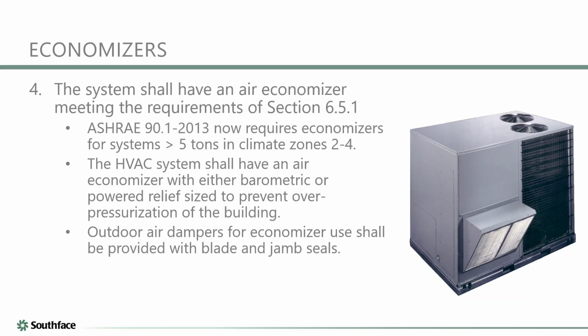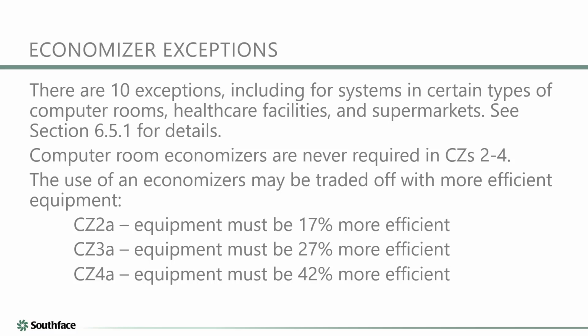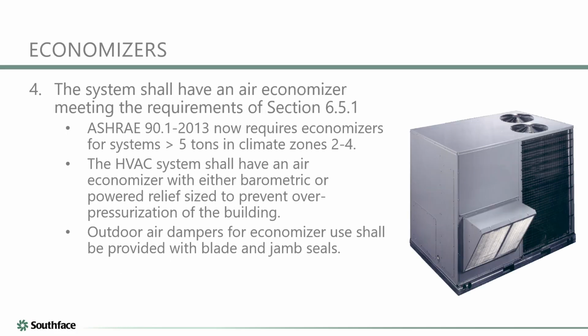Yeah. Because of all these reasons, if you look back at the ASHRAE standard over the years, economizers have essentially come and gone from being required in Georgia. In this cycle of the code, it looks like they are now going to be required in Georgia for larger systems. So that's basically just a functionality of your equipment and its controls. If you put this into a building, you're going to be required to have an economizer.